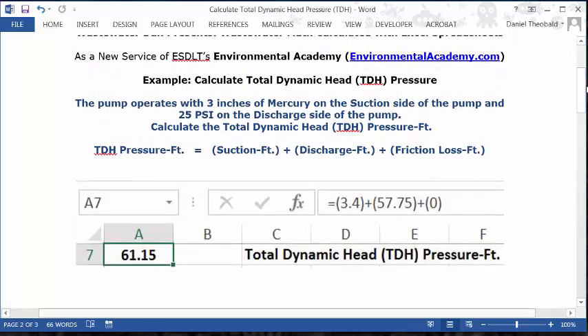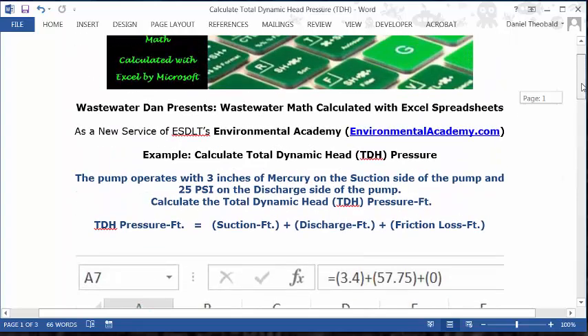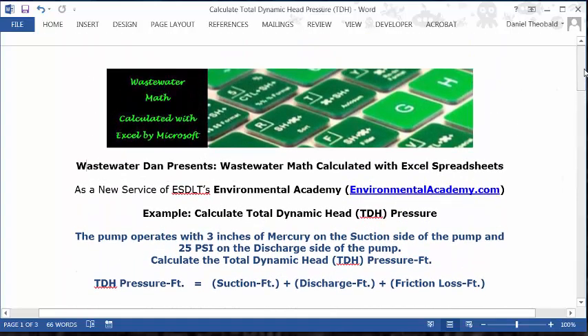We have zero inserted in the formula for friction loss because no friction loss is described in the problem. However, friction loss is included in TDH if the information is provided. It's associated with losses due to angles in the pipes and construction material — for example, cast iron might have a certain friction loss that PVC pipe may not. If you're given that information, you can put it into the formula as well.